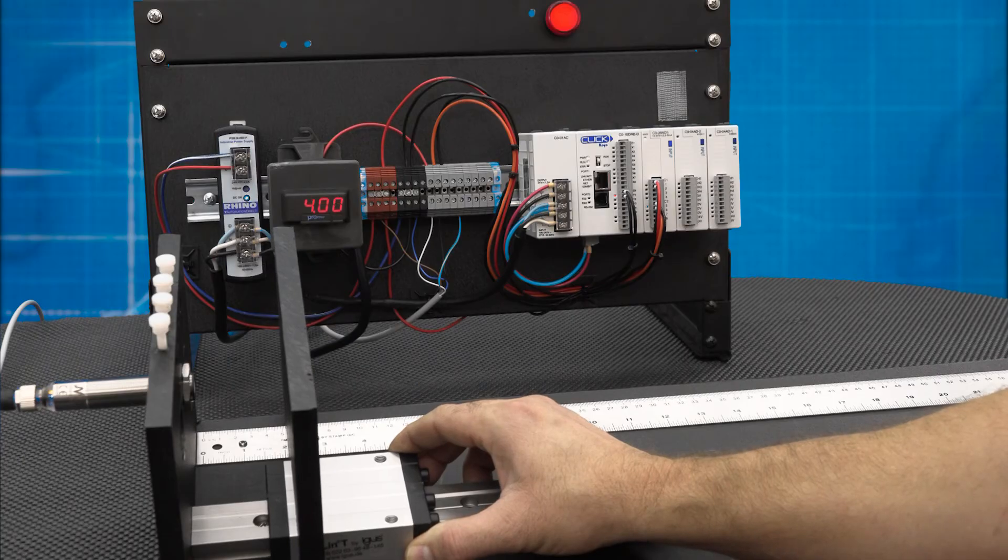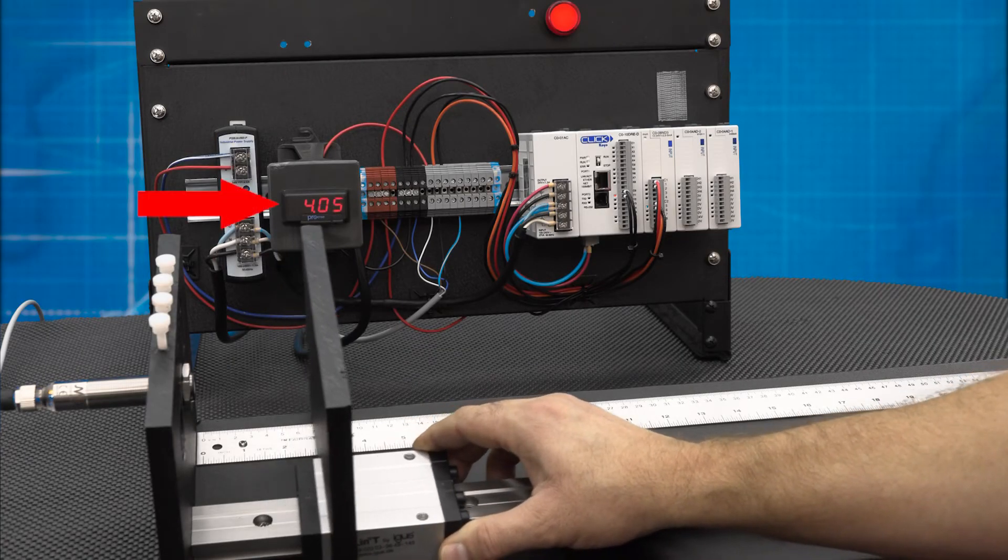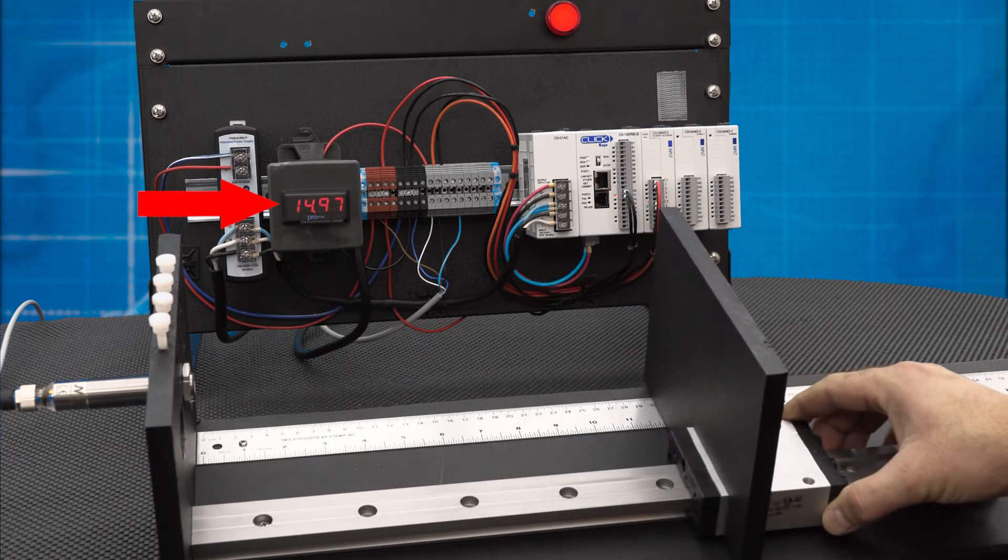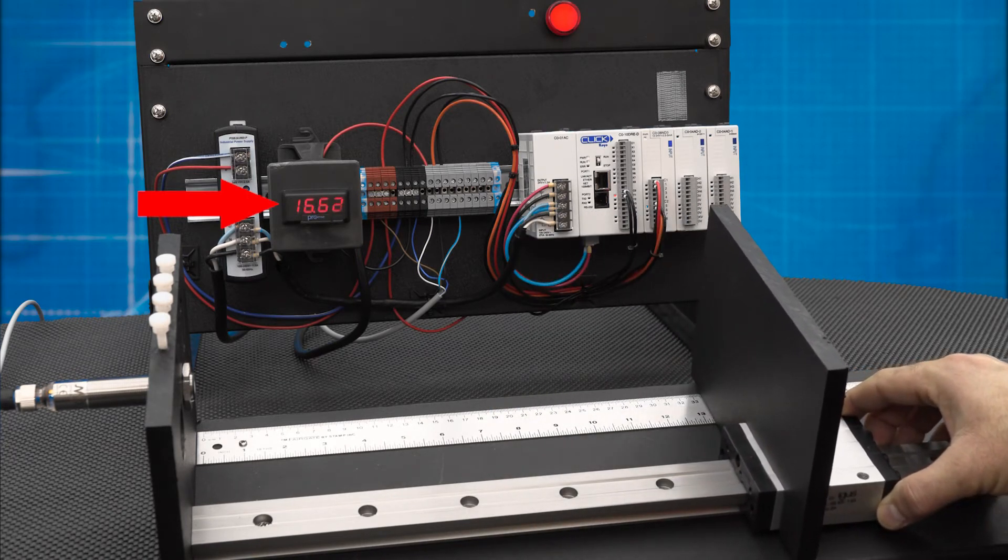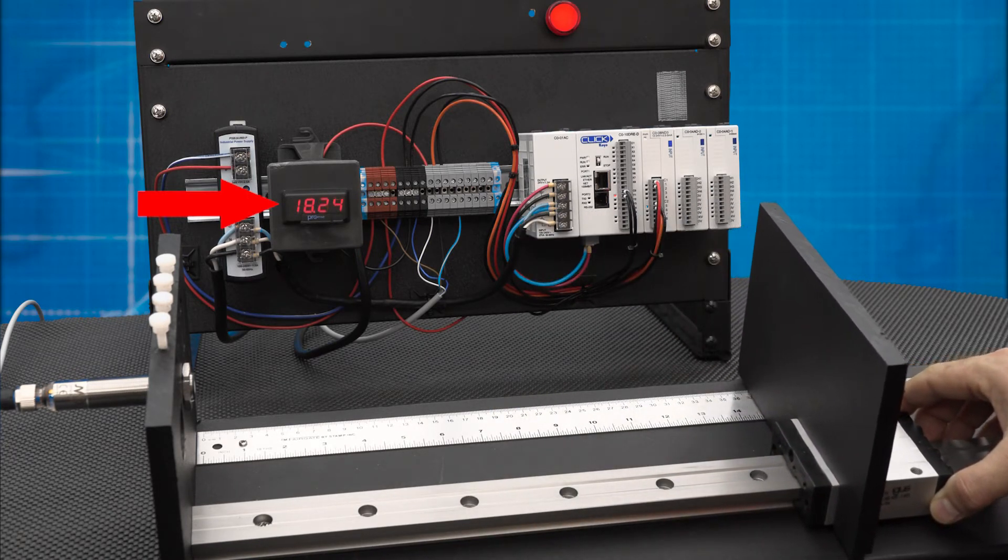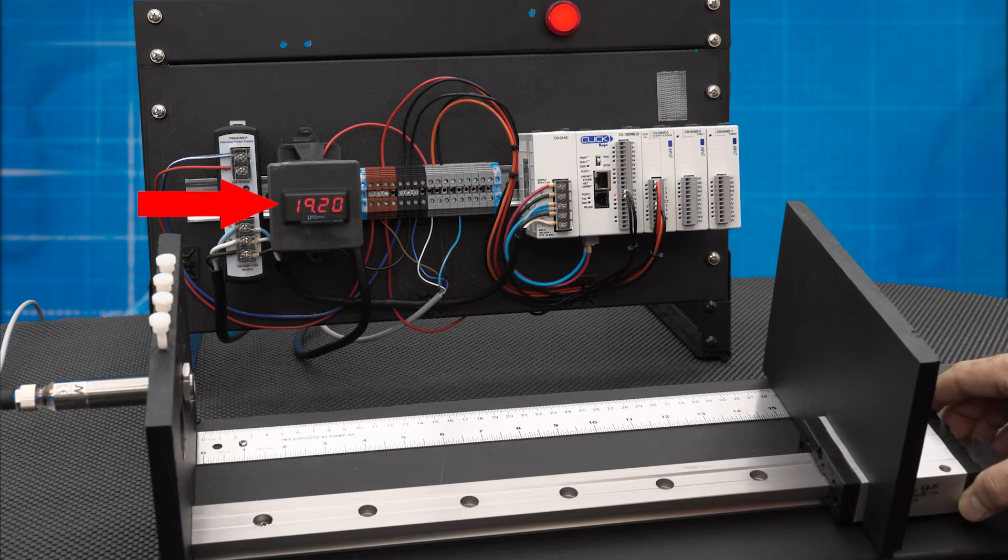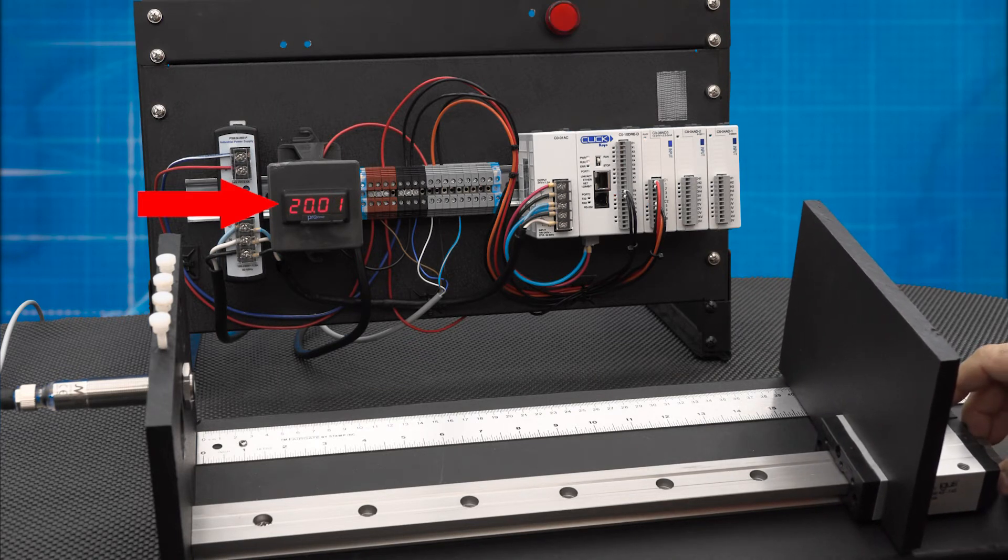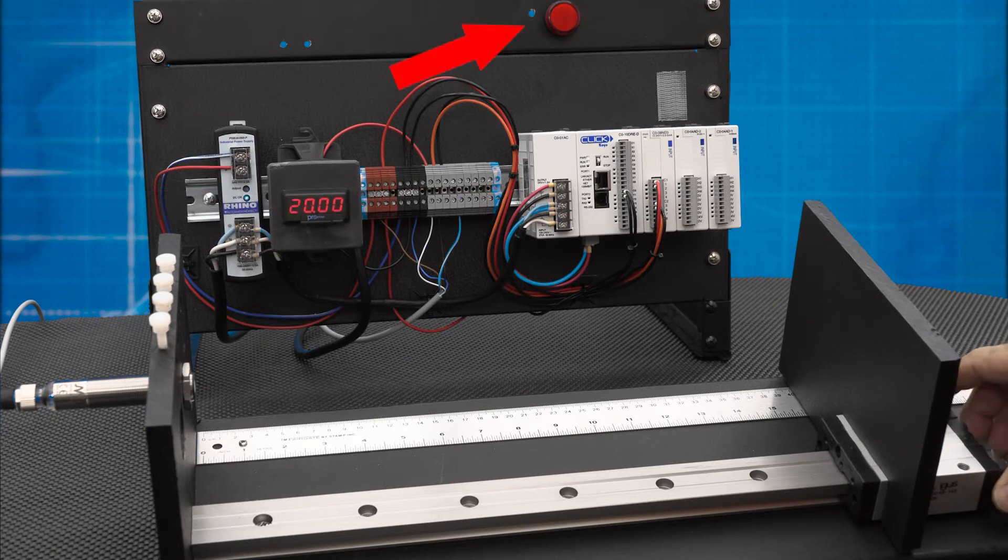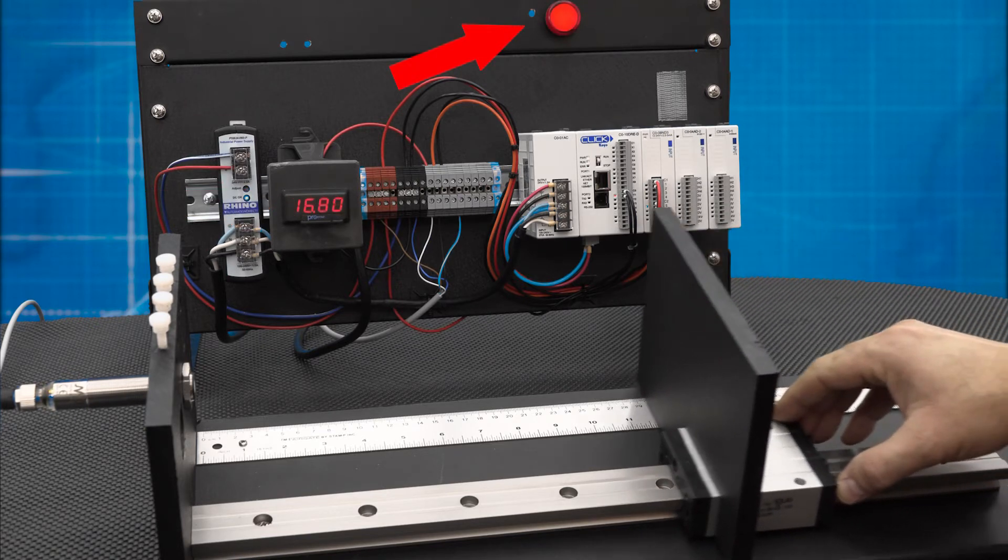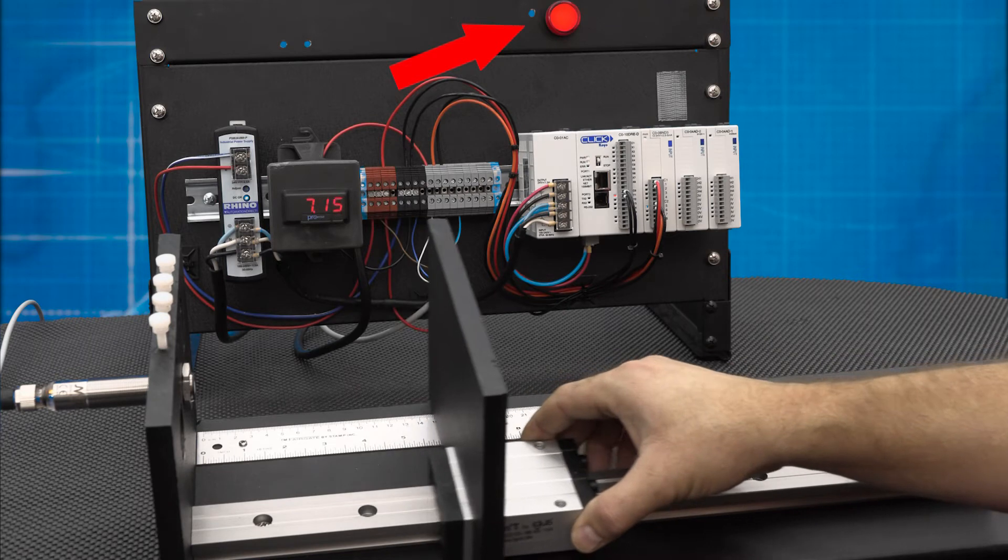As you can see, at 4 inches our analog signal is reading 4. As we increase the target distance to 14 inches, our analog signal increases to 20 or has a positive slope. At 14 inches, our discrete output comes on and stays on until we get to 4 inches, then turns off.